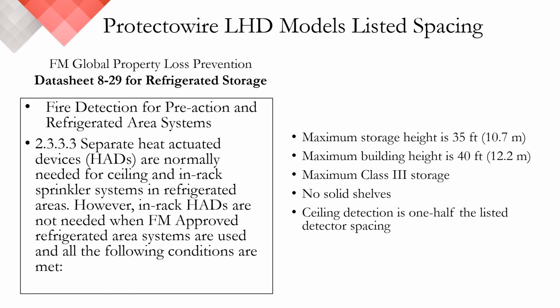Information like this is the reason that we use the word typical so often in the special hazard industry. While the physical measurements of 35 feet and 40 feet are clear, we've seen a variety of interpretations. Some are rather outrageous and others are very literal to find a way to apply subjective interpretations to these objective values. So for example, with a maximum storage height being 35 feet, how is detection designed for a building that has racks up to 40 feet? But maybe they don't use the top 5 feet of the storage. Another example is what happens when a maximum building height is measured to be the distance from the highest point of the racking system, rather than the floor or the ground floor, to the lowest point of the building roof. I bring up these examples to highlight how important it is to understand what is needed from the detection system.